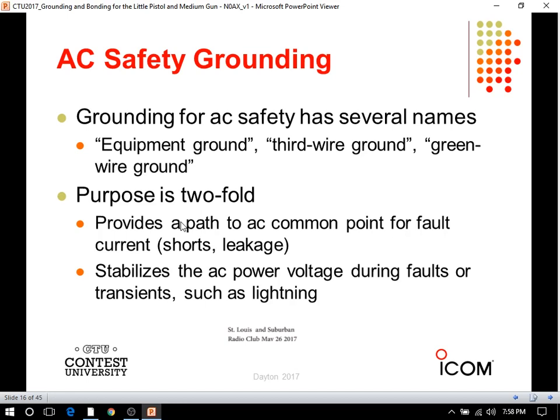And the other thing that it does is it stabilizes your AC power voltage during faults or transients, such as a lightning strike on the power grid, or perhaps a branch falls down and does a phase fault, or something happens and there's a big fault in the power system someplace. Big transients can come rocketing down the line. So all these little pole grounds and the grounds at each house, all they do is try to stabilize that voltage so that half of the system doesn't go to 3 kV for half a second. So that's the twofold reason to have AC safety grounding.